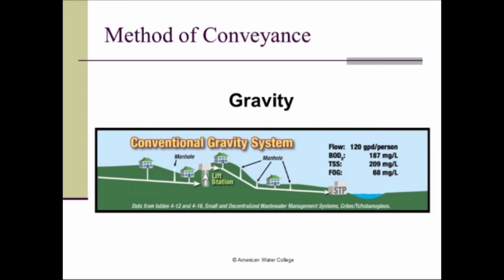In a gravity system, you have residences on a slightly sloping terrain. As the wastewater flows, it gets to a point where we need to use a lift station to lift it to a higher elevation and then on to the wastewater treatment plant. What's happening is the depth of the trench is getting too deep, so we raise it back up to a higher elevation. Without a lift station, the sewer system would have to maintain a very deep trench — especially to serve a house on a hill. So gravity moves the flow, assisted by a lift station.